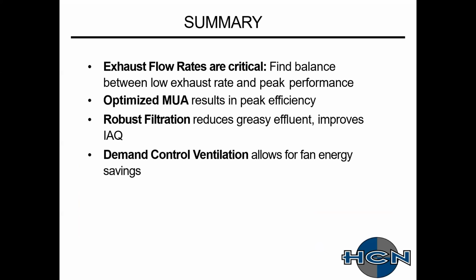So kind of summarizing what we talked about today: lowering your exhaust flow rates is critical, finding that balance between low exhaust and peak performance. Optimizing your makeup air, how you introduce that makeup air into the space, is very critical to how well your hood system is going to perform. Your hood is, I wouldn't say the brain, but it's definitely an important part of it. Your fans are kind of the brain, I'd say, in your control system.